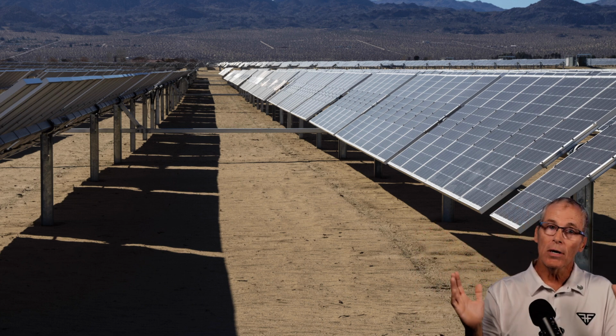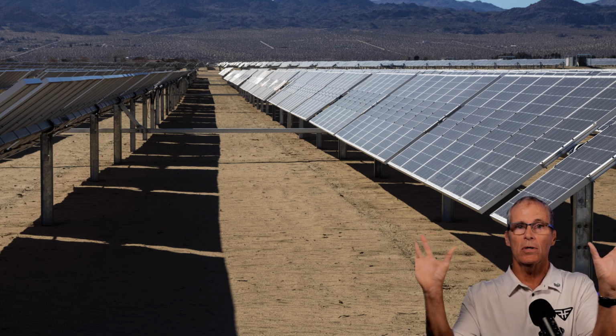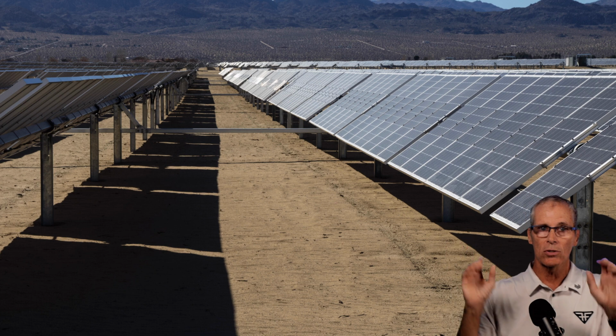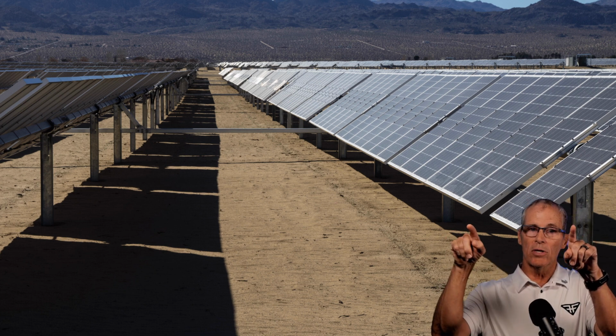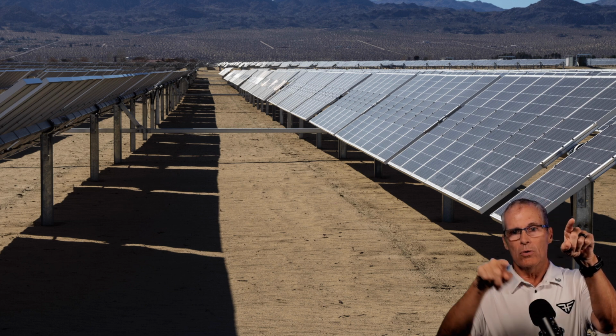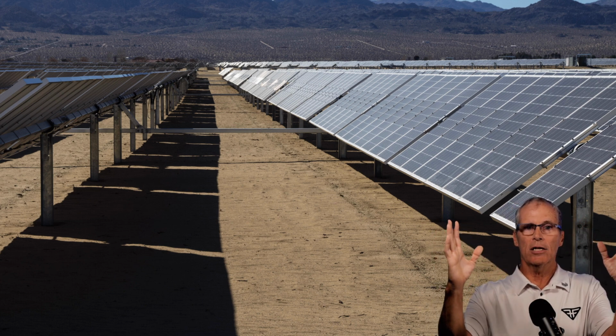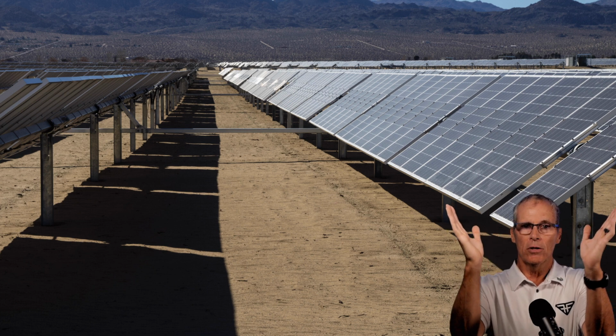So what I saw out in the field is, the ones that went between the panels were all loose and proper, no stress on their connectors. But at these columns and these supports for the racks, the jumpers were tight because they had to go across this gap, this 8-inch gap instead of a 3/4 inch gap. They're just down here tight.